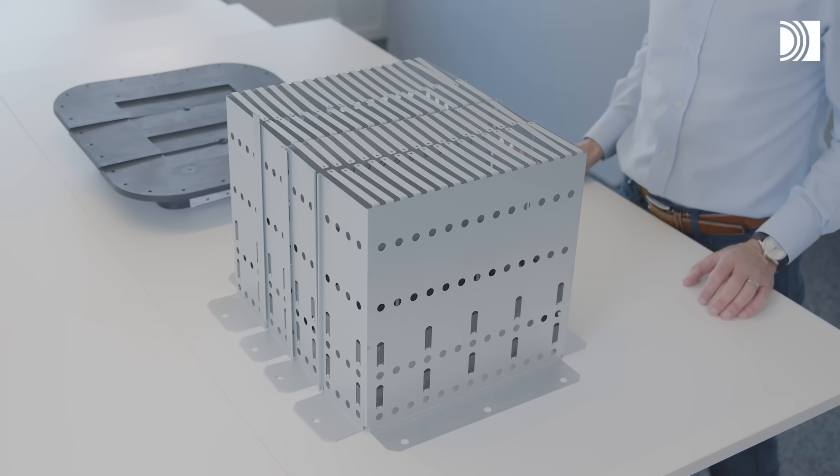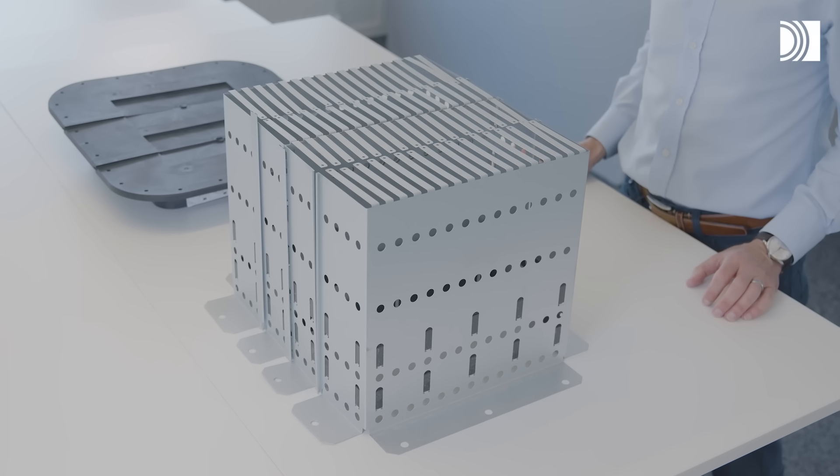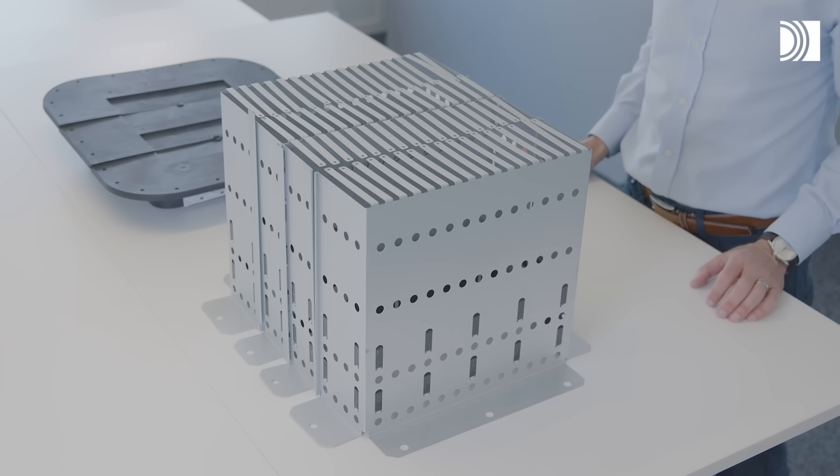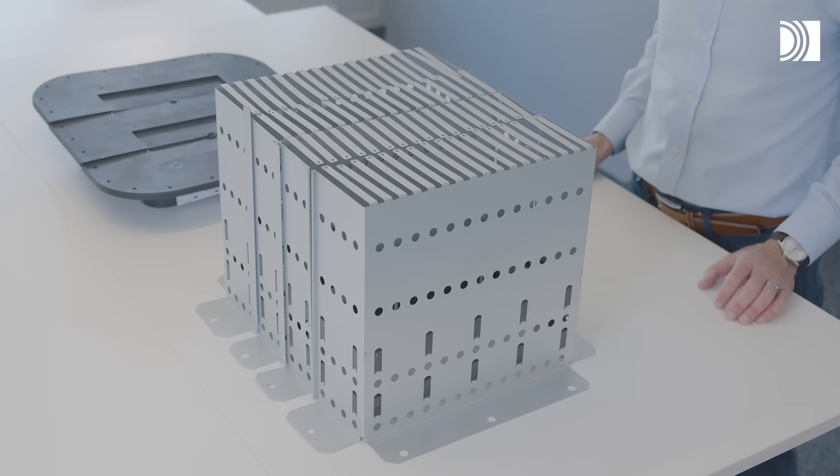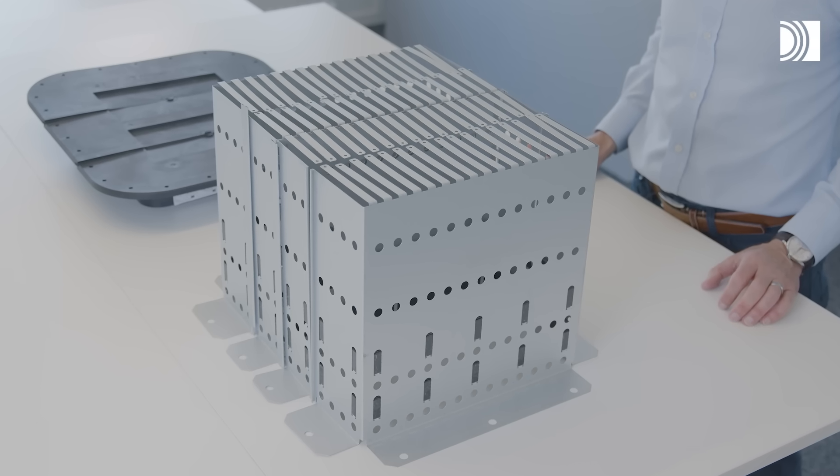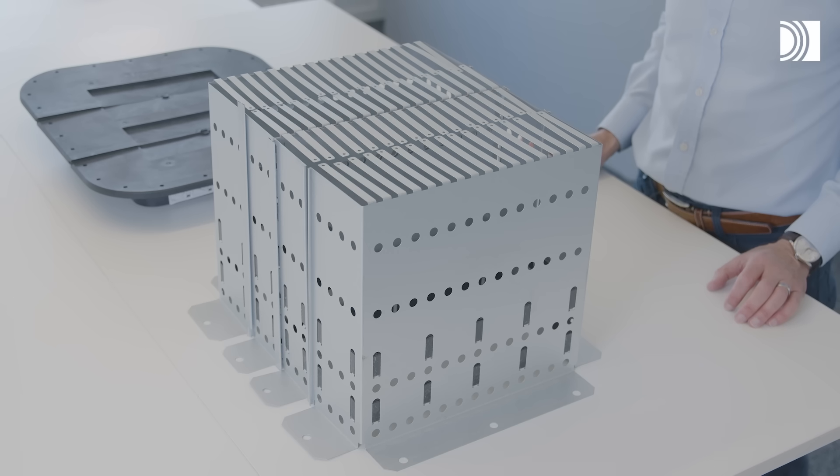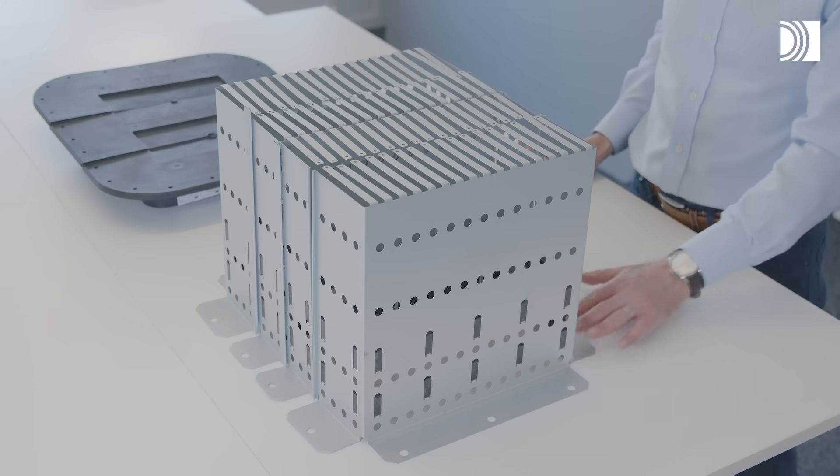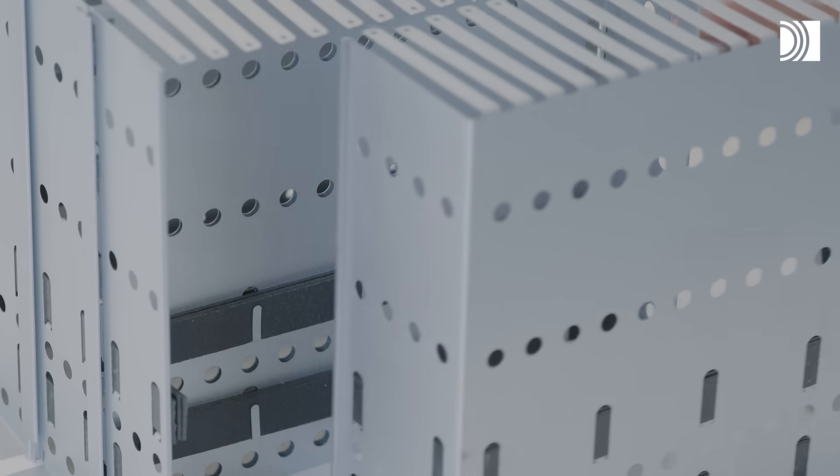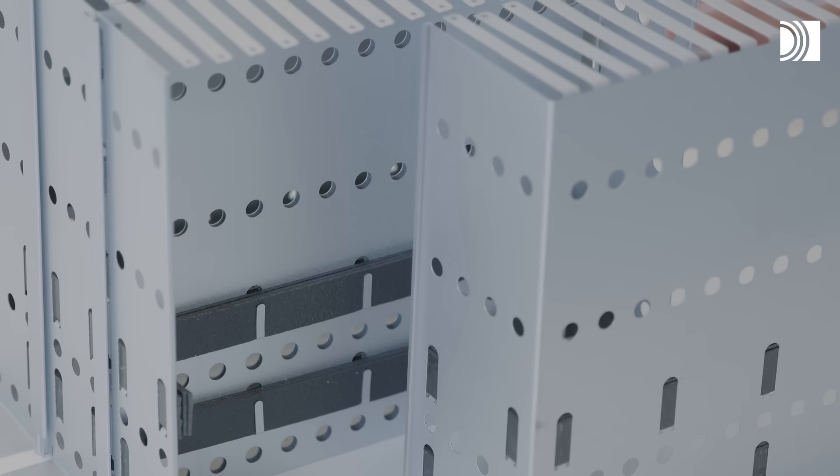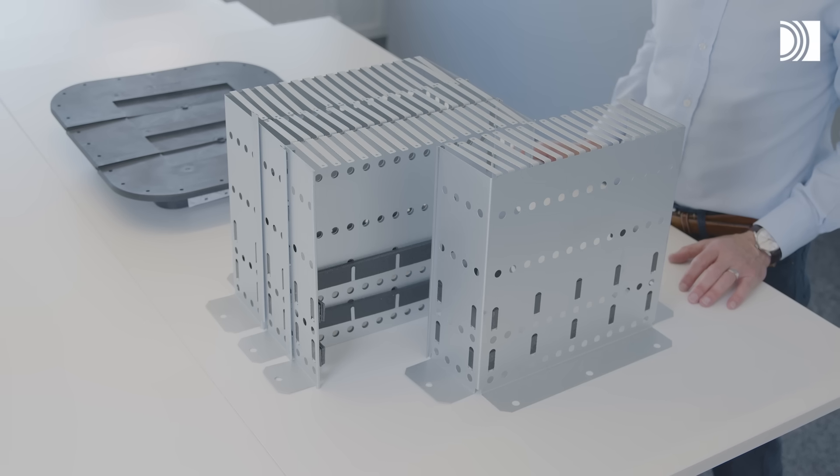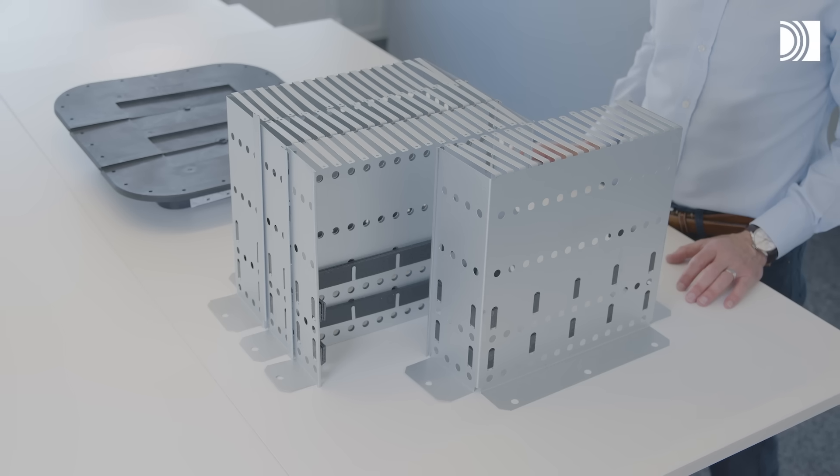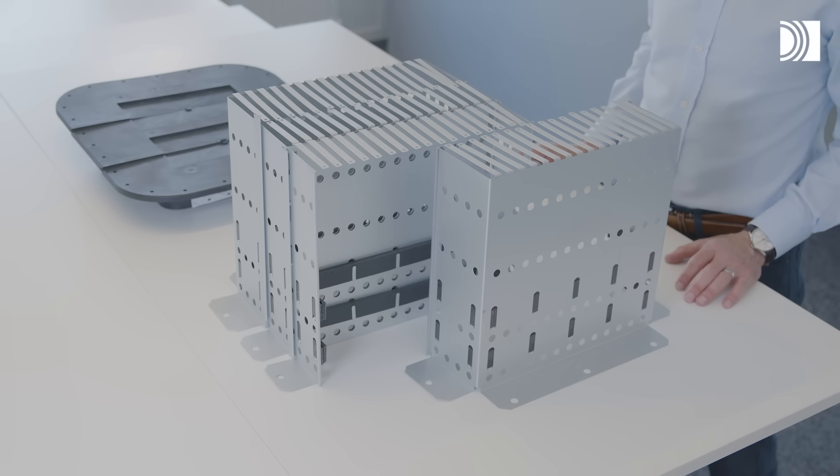Or you add this smart extension frame to the opposite side of the wall. It's the ideal choice when you don't want any fire insulation at all. The extension frame includes intumescent material that expands when exposed to fire, meaning you can avoid time-consuming insulation wrapping.